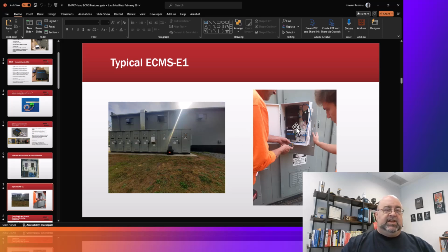The nice thing is the remote PC is a fanless PC, so it keeps it warm in the winter, and then the box is set up and selected, and how we laid it all out was to allow for pulling in an exhaust of heat that allows it to stay relatively cool during the summer and can hit 70 degrees centigrade inside here before there's any issues. All the components are selected for that.